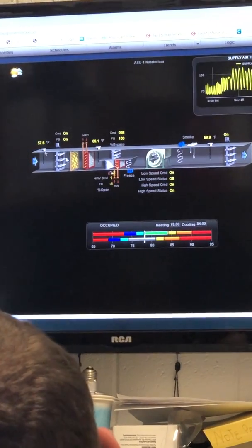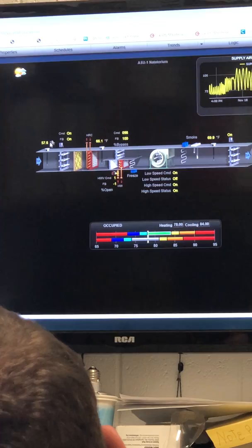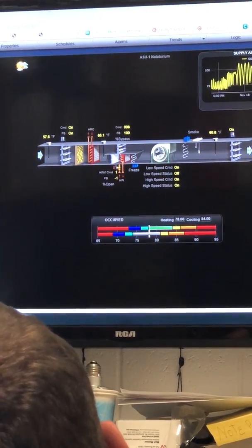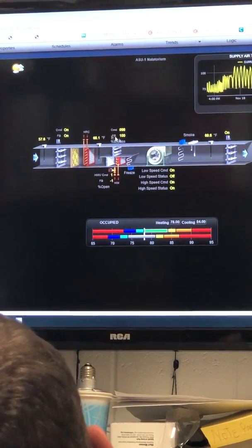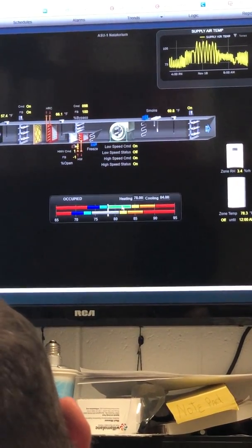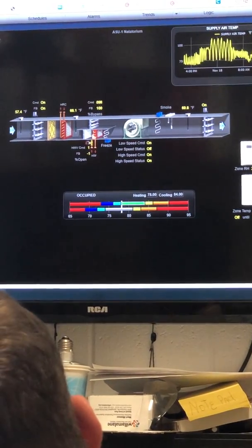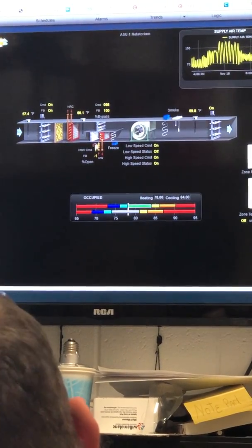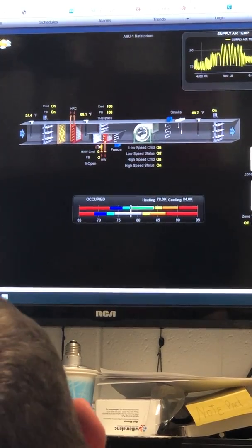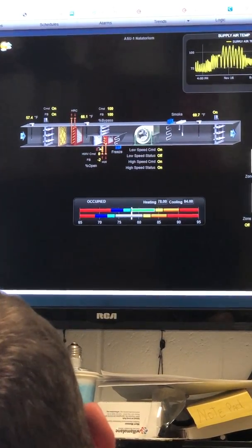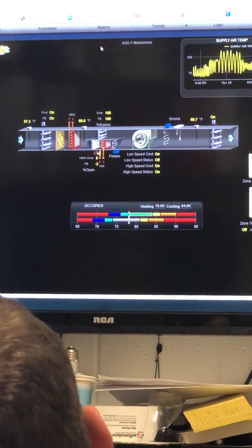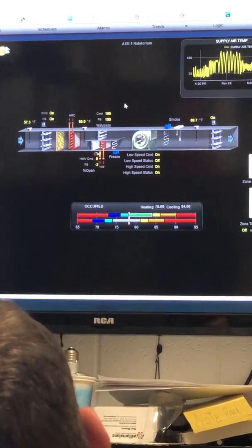Yep. So as far as control points, right here we have outside air temperature, which is driving, in a sense, let's go here, the heat coil. So the supply or desired air temperature is what's driving this heat coil. So there's a control point. We get a command to run for the fan. That's because it's occupied, so there's another control point. This bypass damper control is another control point as well.